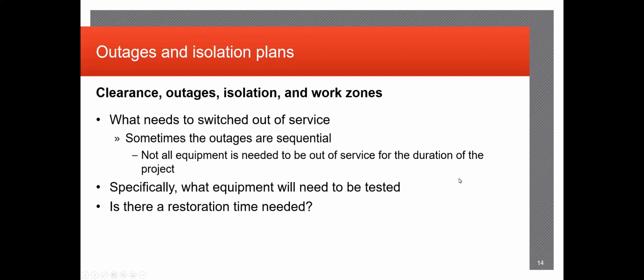So sometimes you'll have to identify which piece of equipment needs to come out first, which comes out second, et cetera, et cetera. And then once everything is placed out of service, you need to identify what equipment needs to be tested, whether that be new equipment that they're just going to be placing into service, or if it's going to be upgraded equipment, if you're replacing a relay of sorts, stuff like that. And then restoration time, what would that look like? Is it going to be pretty substantial? For example, for a new transformer that's going to be placed into service, you actually energize it, and then you have to wait. There's a 24-hour waiting period to let the transformer soak. And then usually oil samples will be taken, tested, and measured to make sure that there were no anomalies during the 24-hour period. Stuff like that should be recognized prior to, so that nothing weird comes up when the client's asking why everything's not up and running yet.